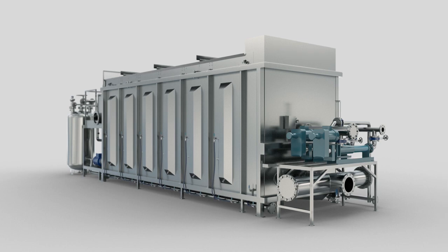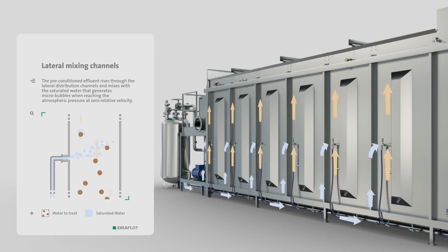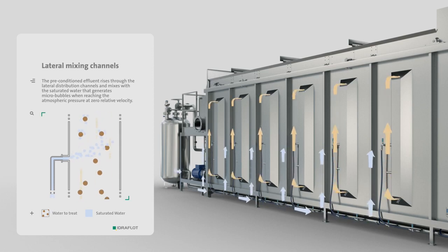The flow divided into the lateral mixing channels, present on the outside of each flotation module, is mixed with saturated water. The sharp drop in pressure develops micro-bubbles which adhere to the flocs.